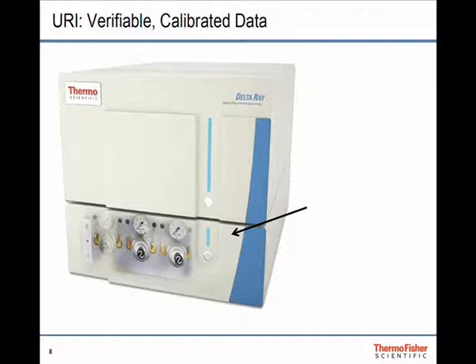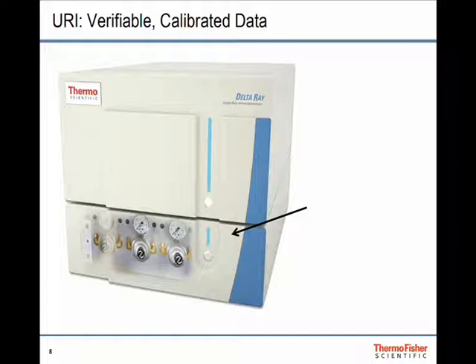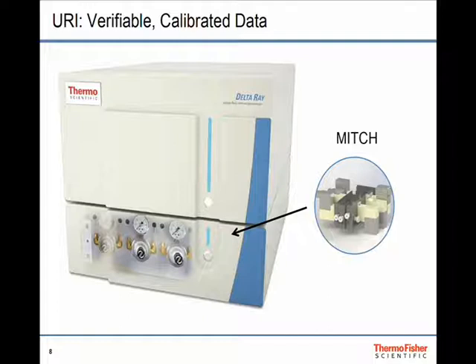I've showed you how a mid-infrared platform is pretty simple and you get very good performance out of it, good precision. Now what does the URI, the Universal Reference Interface, add? It essentially provides you with verifiable and calibrated data. At the core of the URI is what we call the MITCH, a mixing and switching device. It's a micromachined precision engineered piece of equipment that allows you to mix the different gases.